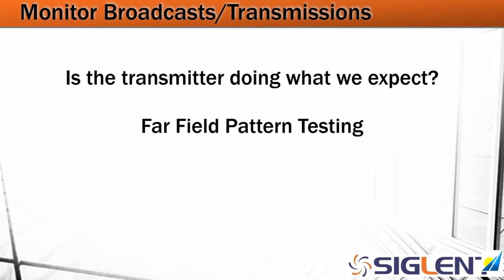Far field pattern testing — are we transmitting properly in a particular direction? Are we expecting a certain amount of output power at a particular point in space and not actually getting that? You can walk or even drive around your transmitter and test in different places to make sure that you're getting the right amount of power where you expect it.